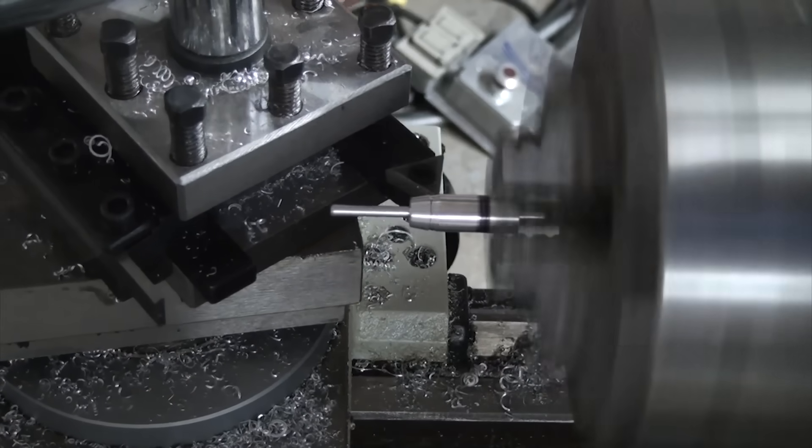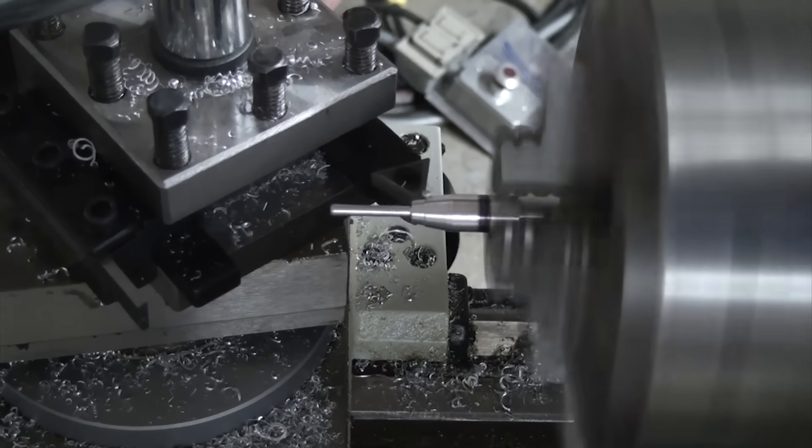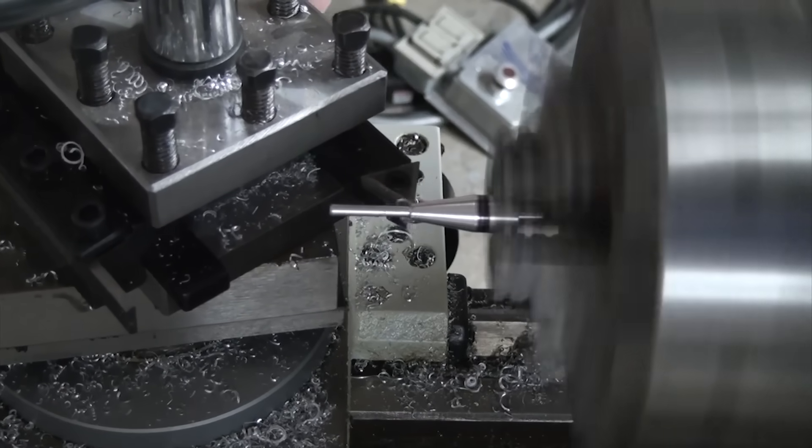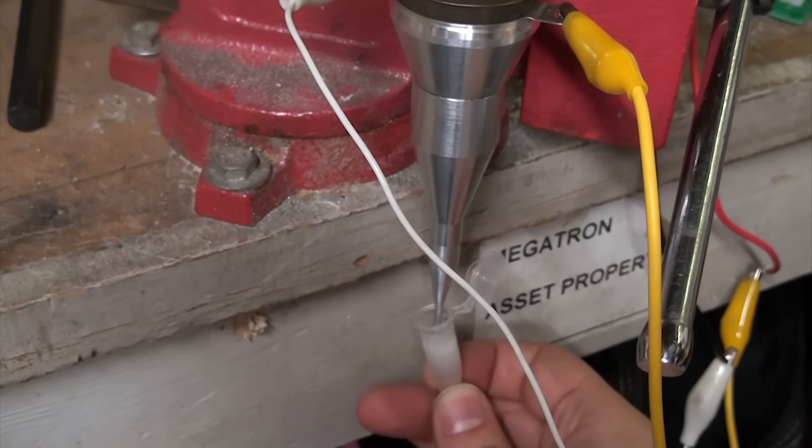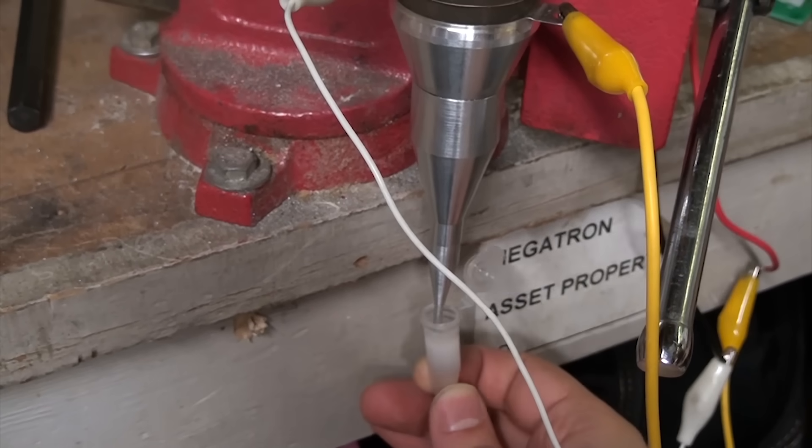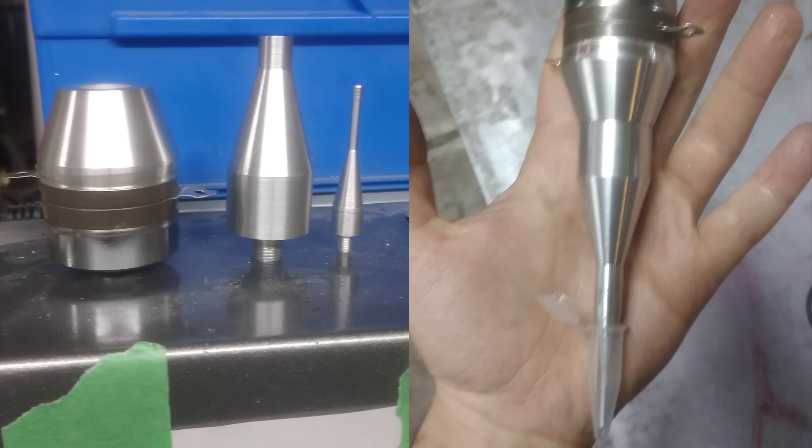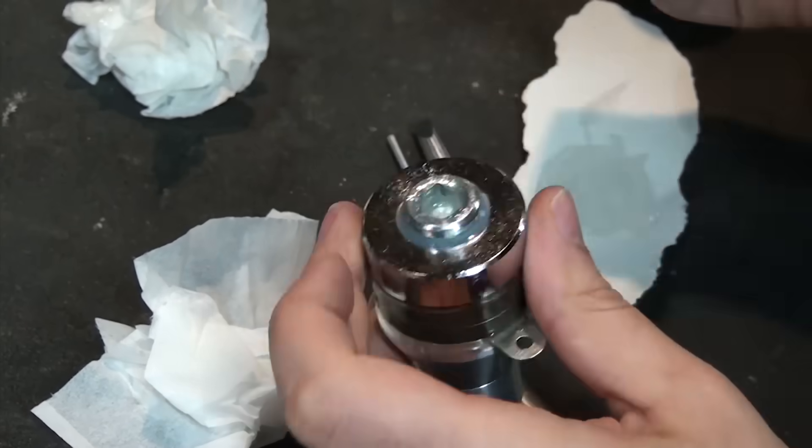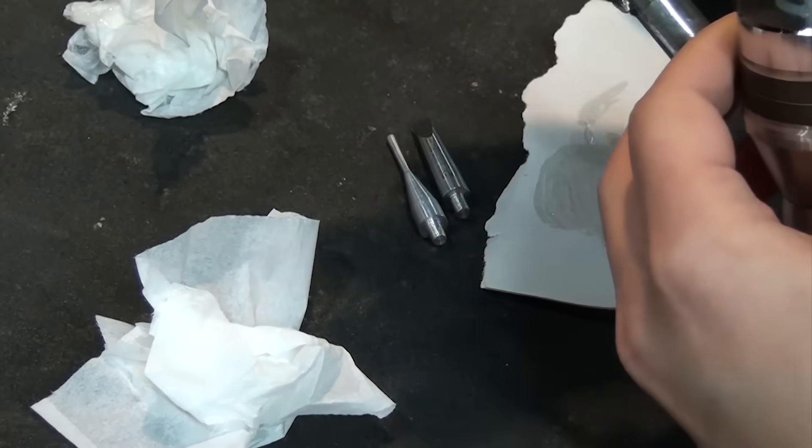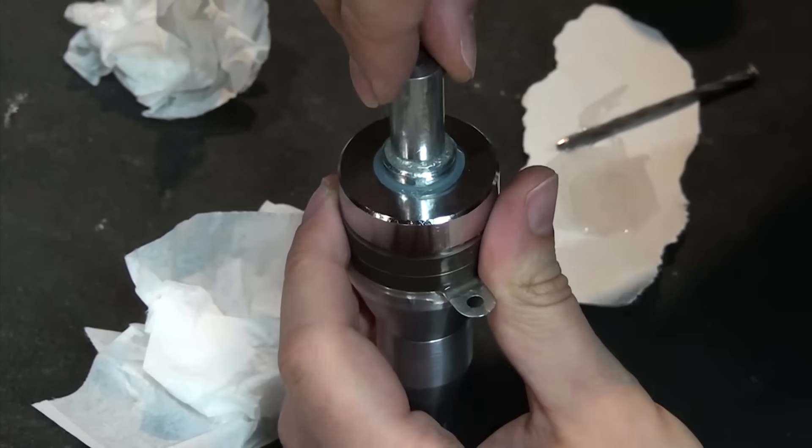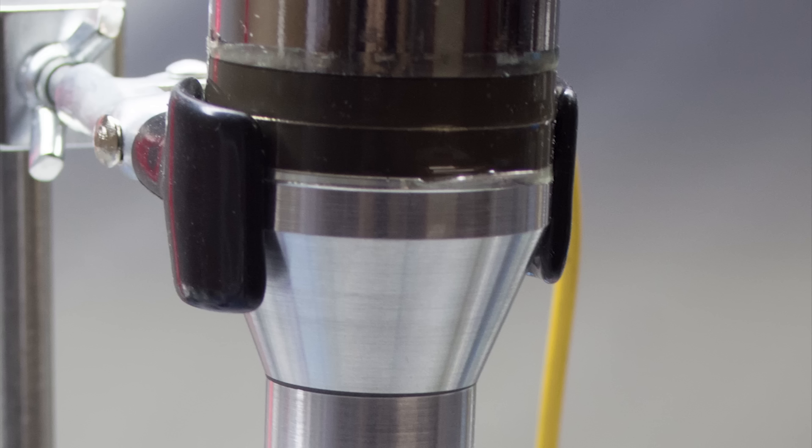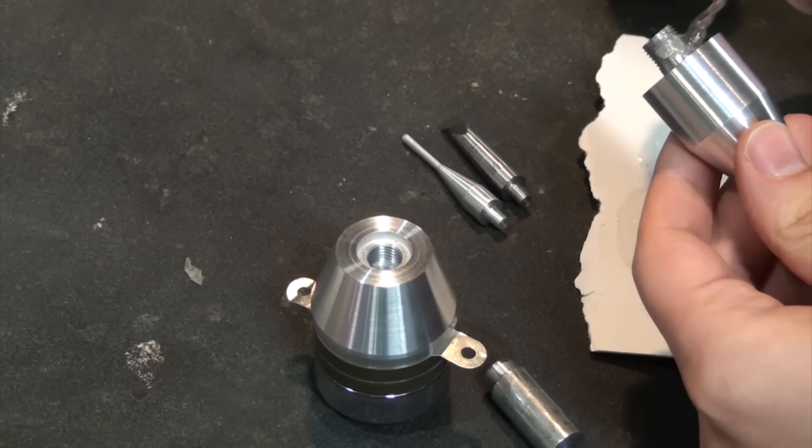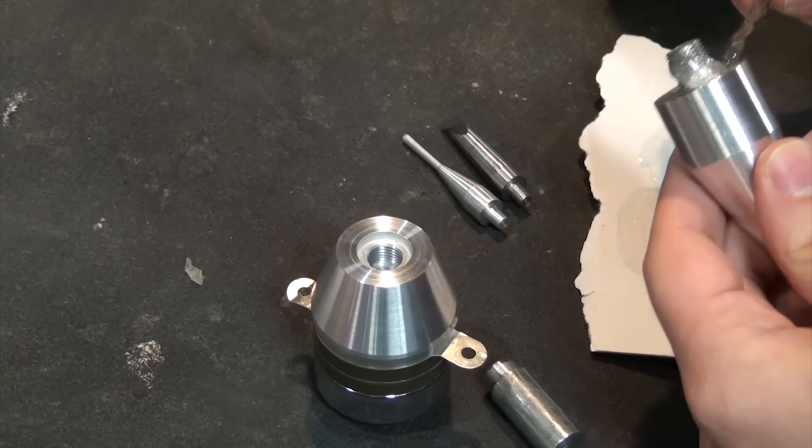And finally to finish this first draft of the horn, we made a little aluminum piece to fit into the end that had a final diameter of about 3.5mm. The idea being was that this was the size needed to fit into the bottom of an Eppendorf tube. Now at this point I knew nothing about ultrasonics and was making this up as I went, so the geometry was super off, and to add insult to injury I epoxied in a steel nub on the end to be something to grab onto for mounting, since I didn't know how you're supposed to hold these. You're actually supposed to grab these by the working end and find nodal points and there's a whole finesse to it. At this point I also epoxied the transducer to the first insert.